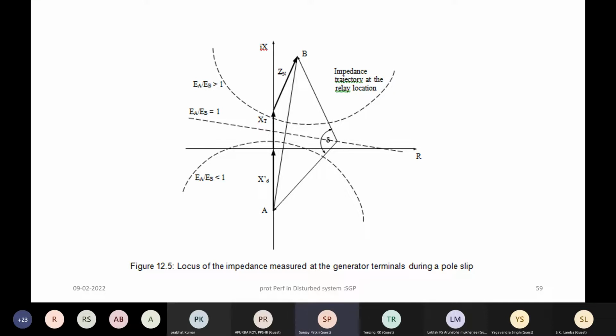Some of these slides I have already explained to you regarding this pole slip phenomenon on the generators, generator transformer and the grid side. So this is basically the impedance line on which the pole slip characteristic is based, a circular characteristic, and this is the pole slip detection swing, which distinguishes between a pole slip within the generator and generator transformer, or beyond the generator transformer. So this line is a dividing line.